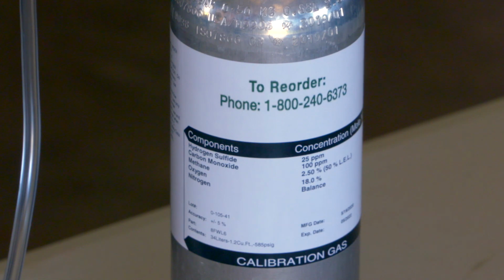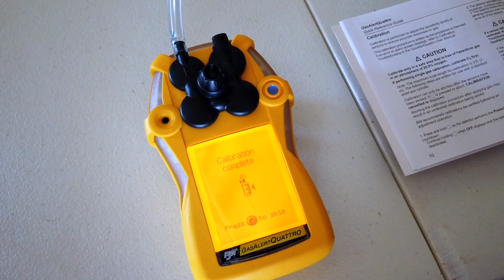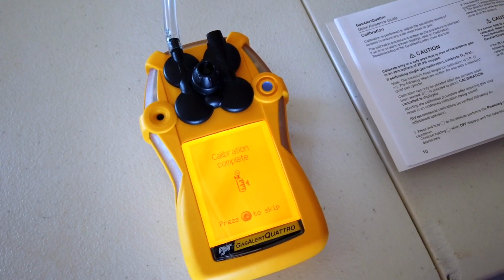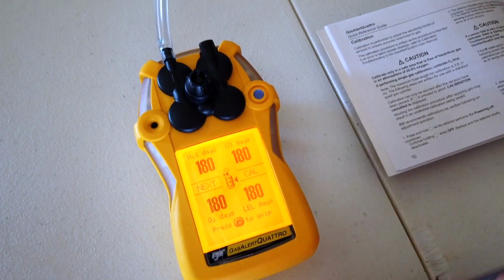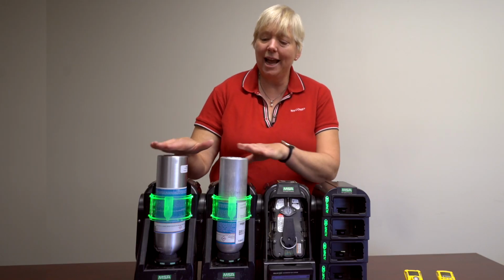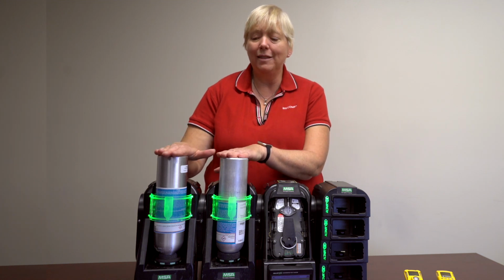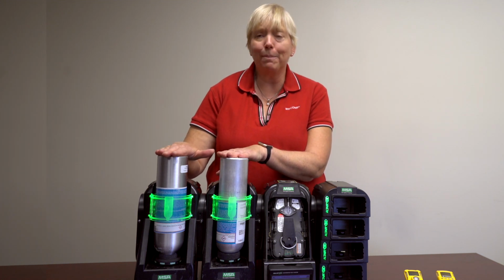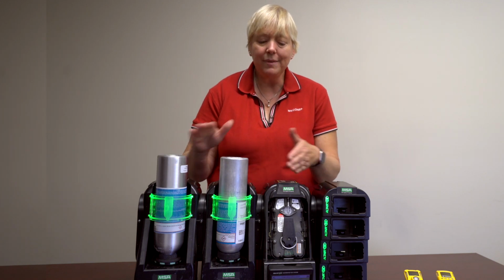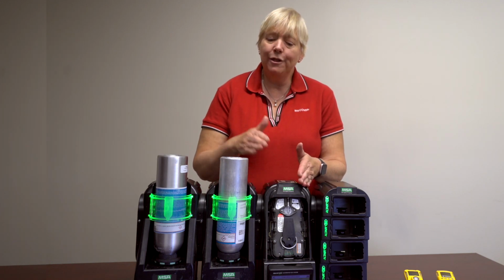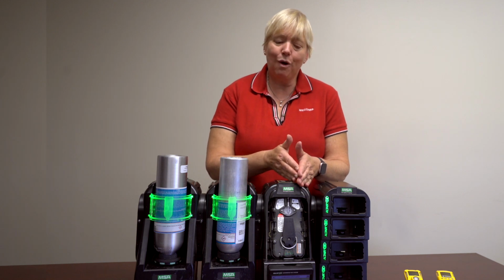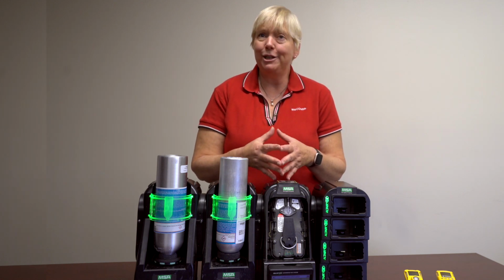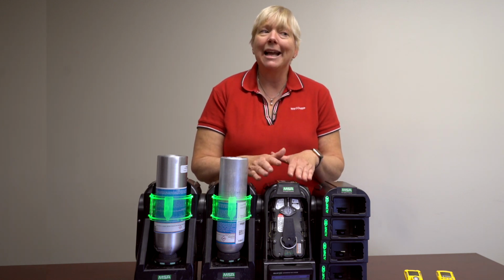It uses a known amount of gas to check that gas against those sensors to see that they are reading correctly. In this unit, the test canisters are ammonia and the mixture for the other gases that are present, such as hydrogen sulfide, oxygen, and methane. The system will read those gases and send it across that sensor to be sure it is properly working.